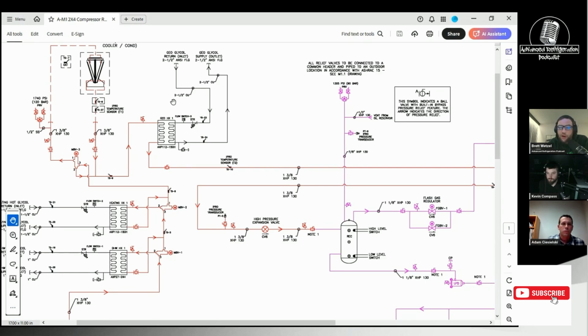Is it going to require more surface area inside in order to get that same amount of refrigerant through, just with the properties of the refrigerant at that point, or no? Yeah, I think I know where you're going with this, and that is a bit unique with transcritical systems. So this drop leg, typically people have questioned, why is a drop leg size so large compared to the inlet size? Typically on an HFC system, we're used to seeing the drop leg, liquid side be a lot smaller than the vapor inlet side.